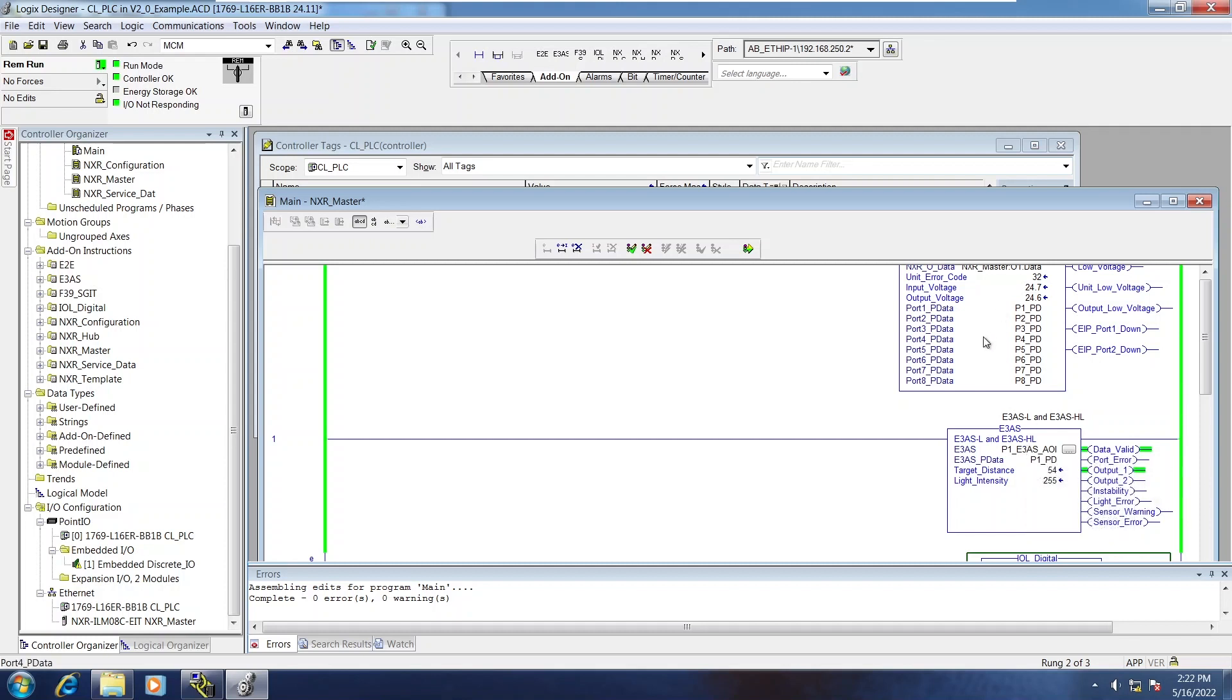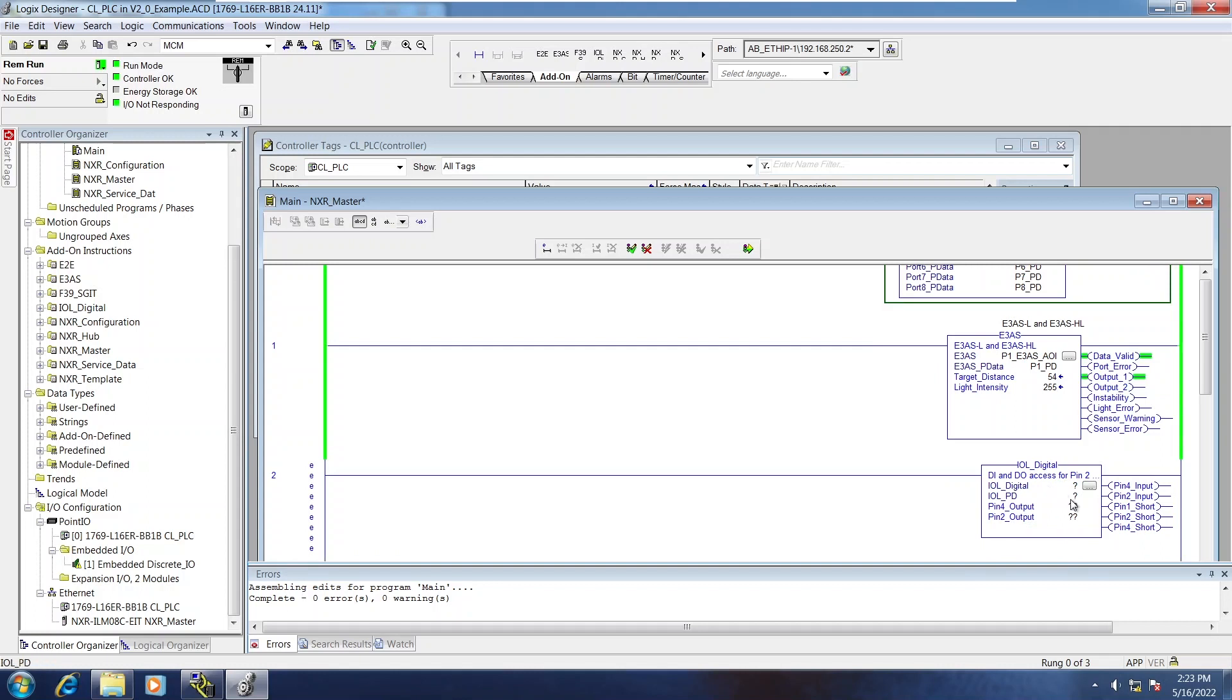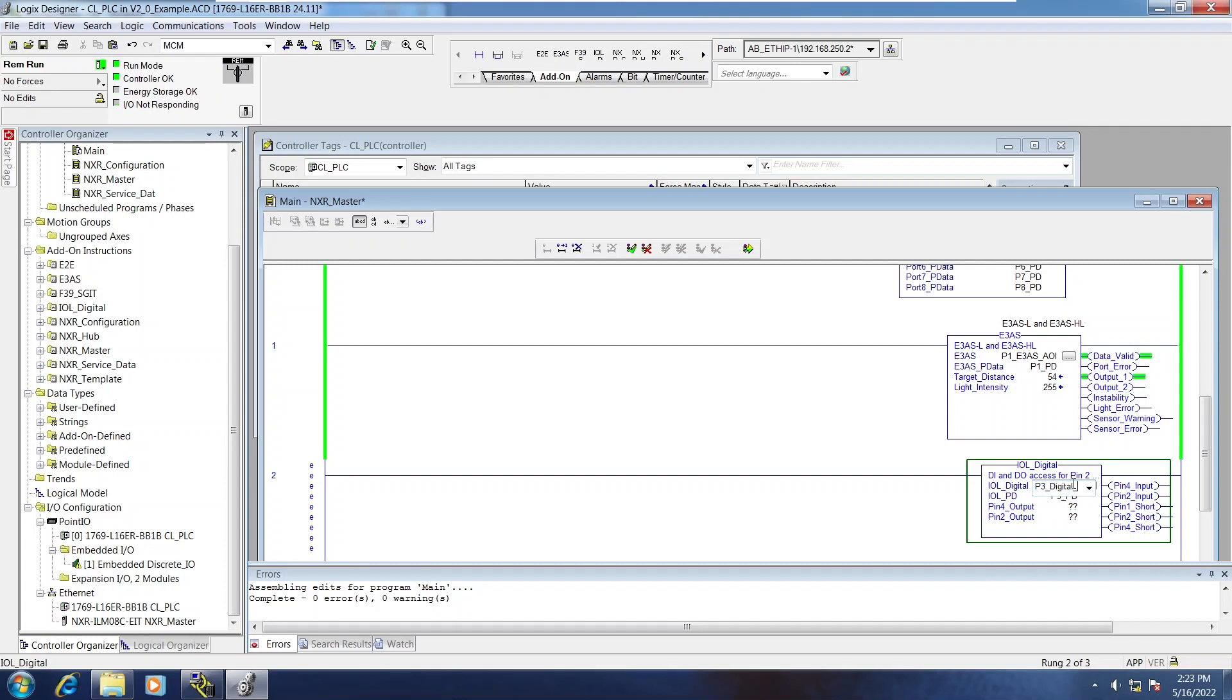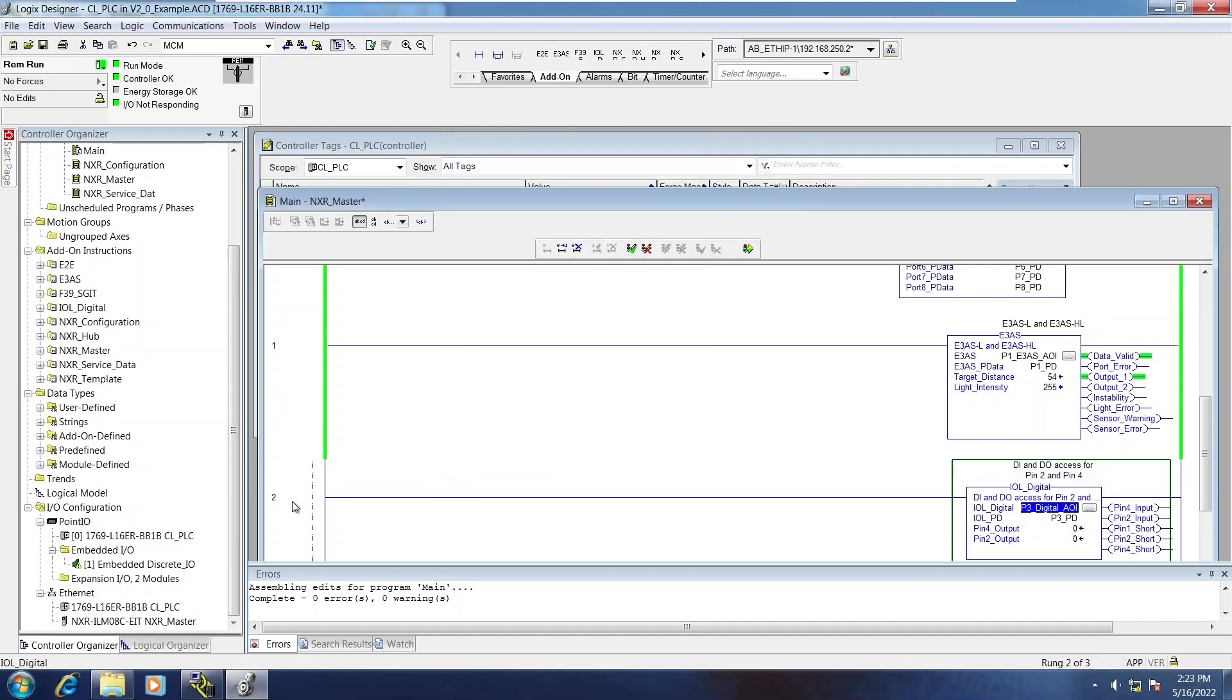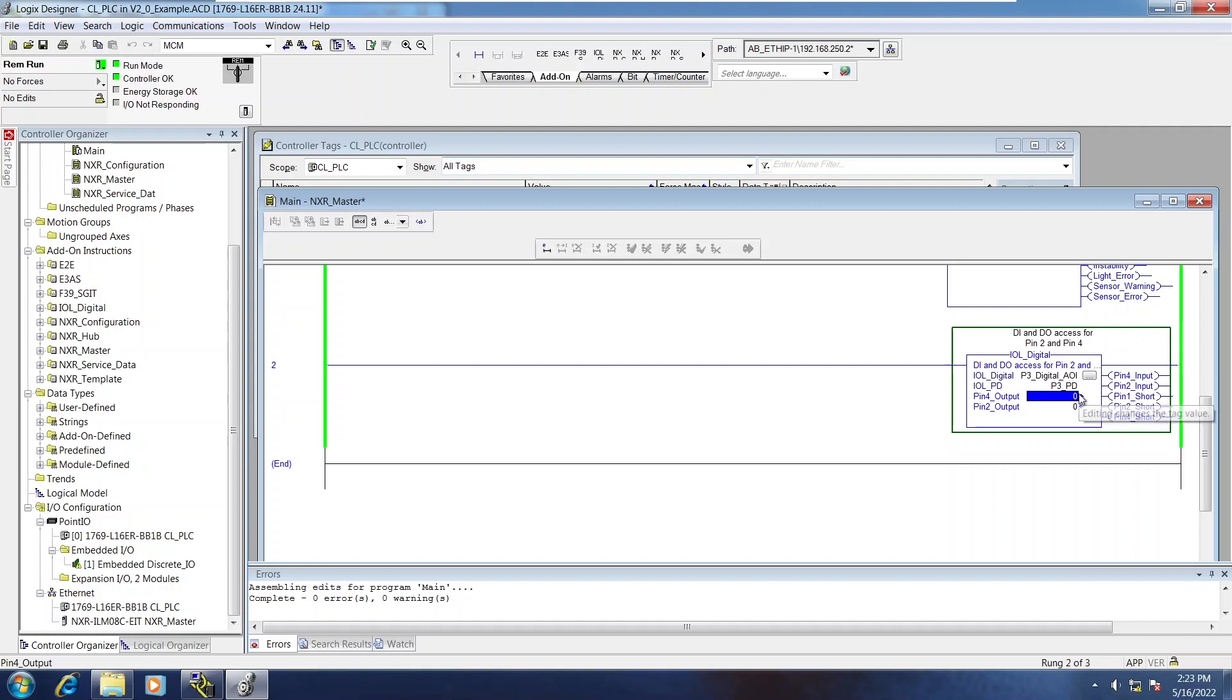So I'll grab port 3 process data. And now I have access to just the digital input and the digital output bits for that port, pin 4 and pin 2. And the inputs are displayed on the right hand side of the block. In addition to just digital input and digital output control, there's also short circuit alarms for pins 1, 2 and 4.